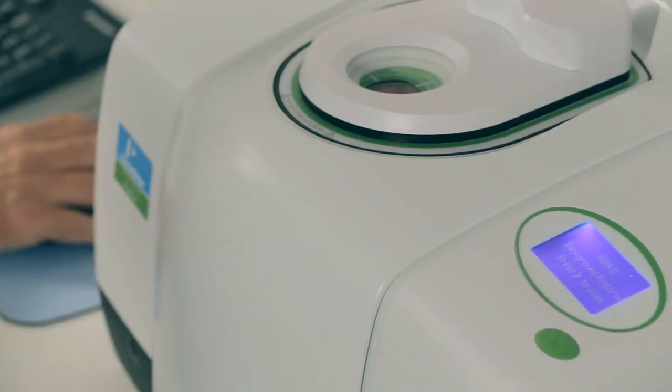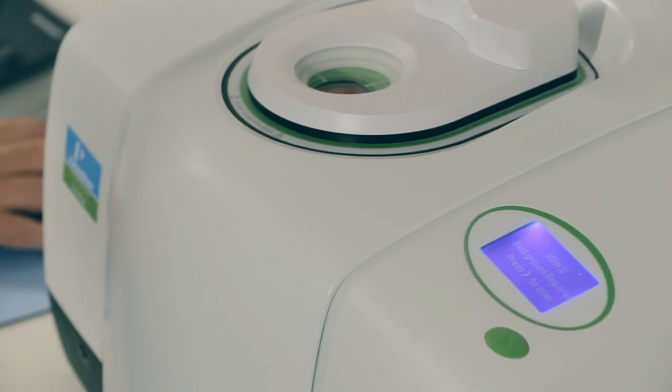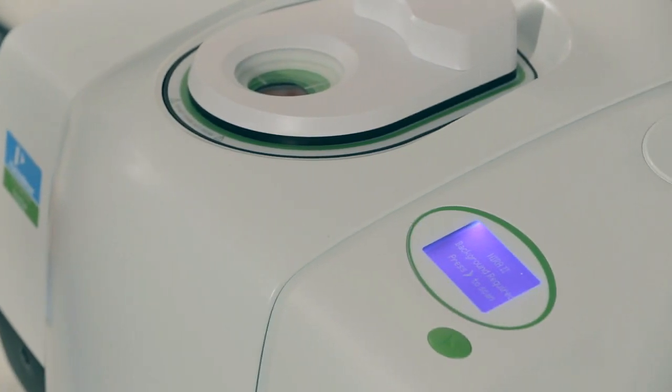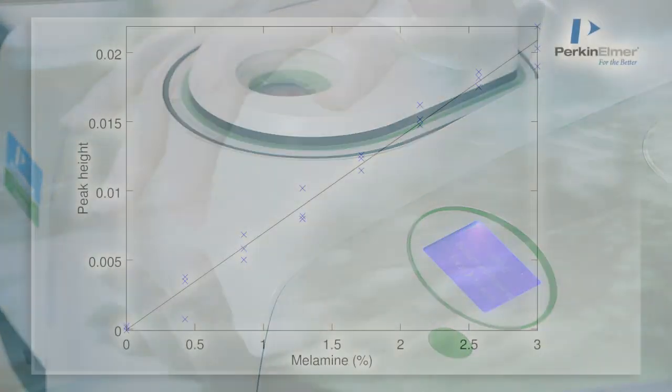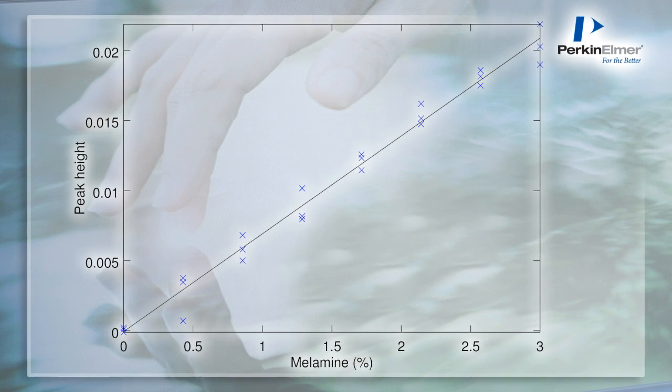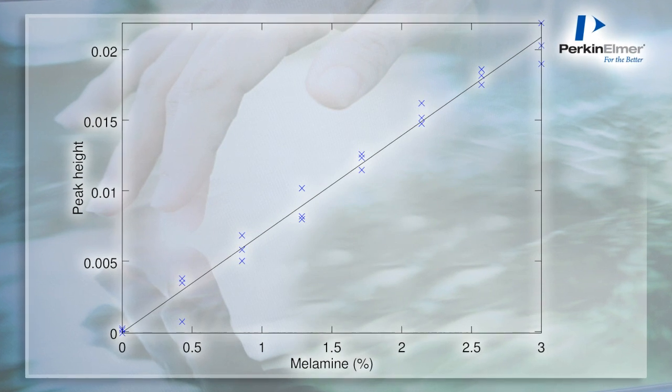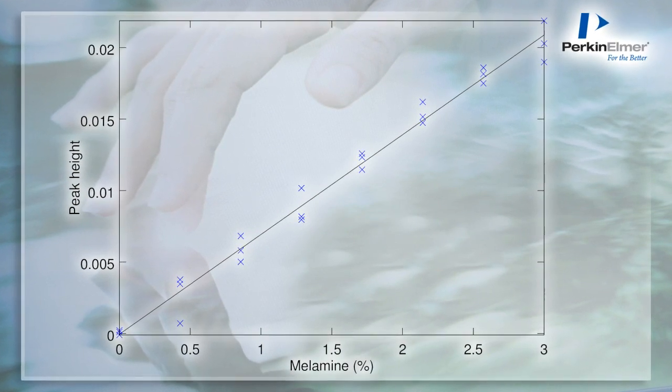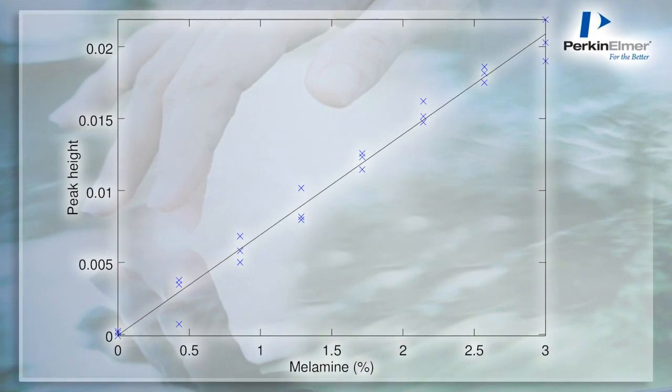Previously there have been two available approaches. The first is to prepare a series of calibration standards with different concentrations of the adulterant, measure the spectra, and then develop a quantitative model for the adulterant. Several publications have shown that this is an effective technique for melamine, but the limitation is that the method development is very time-consuming and in the end you have a method that is specific to just one adulterant.